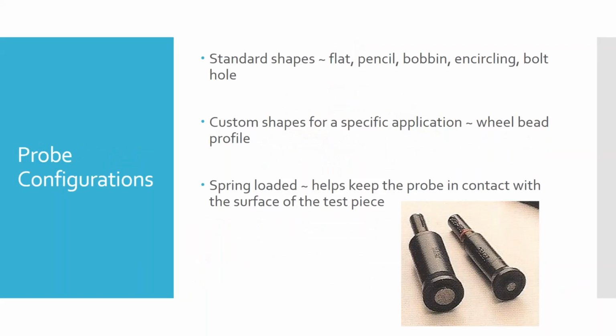So the first one you're going to have here is for flat surfaces. Probes can come in all kinds: flat, and we'll look at pencil probes, bobbins, encircling, and hole probes. But the ones shown here are spring-loaded. So these are a flat probe. They're designed for a flat surface. The majority of this circle is not the probe. The probe is just the lighter gray portion in the center of each of these. The black circles surrounding it are purely a plastic surface to help brace or hold the probe steady, help you keep it steady.